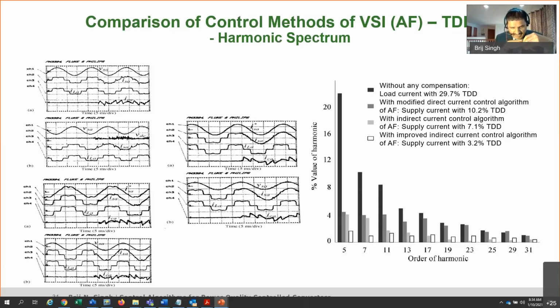When you do passive filtering, you need tuned harmonic filters, such as passive fifth or passive seventh. What remains after that are the 11th, 13th and 17th harmonics, which are dominant. The active filter then doesn't care about specific harmonics since it isn't tuned to any particular one.